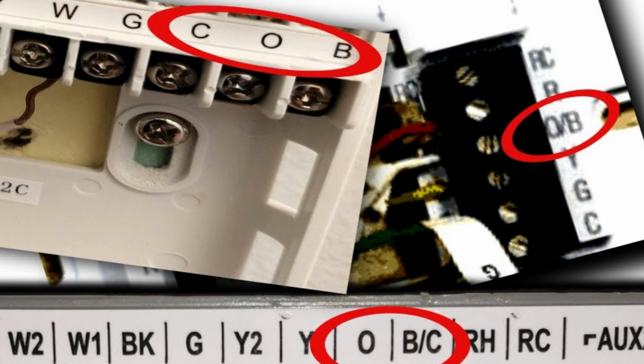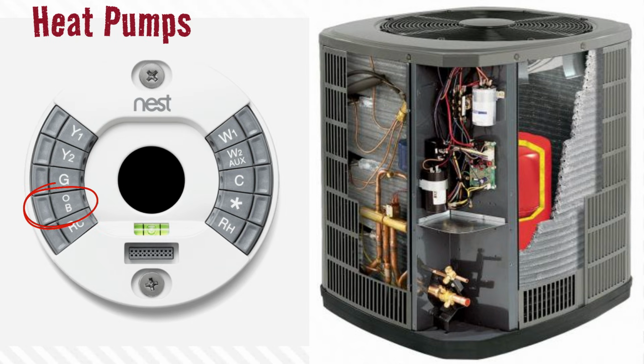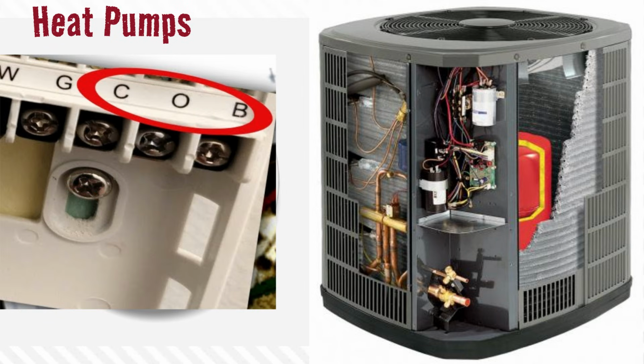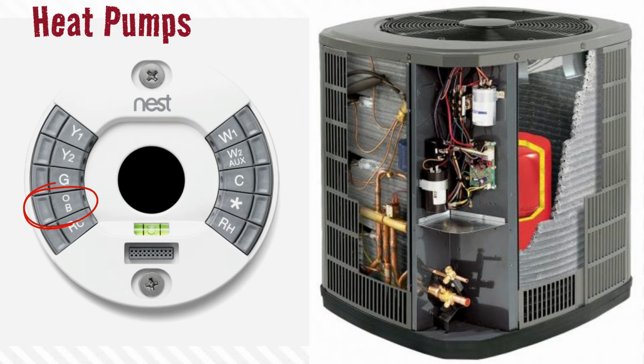Another common pain point a lot of people have is when they're upgrading a heat pump thermostat. A lot of thermostats out there will use various combinations of O, B, and C. Now, a lot of thermostats combine the O and B into a single terminal, and this is for the reversing valve in the outdoor unit to change from heating to cooling mode. Older thermostats used to keep these two terminals separate, so why did they suddenly start combining them into one terminal? The reason for this is because you're never going to use both on a heat pump system.